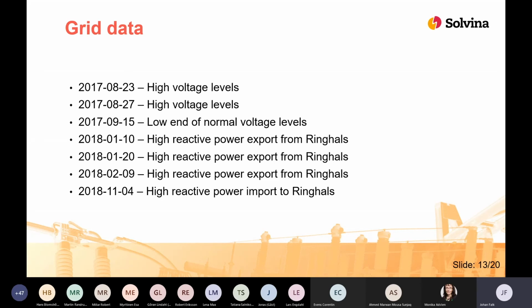First, measurement data was gathered from Ringhals, where we looked at both voltage levels and reactive power. From this data, we have picked a couple of dates for further investigation, and we picked these dates due to them having either low or high voltage levels, or that we could see that Ringhals was producing or absorbing a lot of reactive power. In this list, we can see the dates that are included in the report. I will only talk briefly about 3 of these dates due to time.